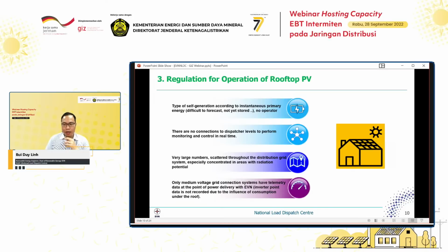Here are some features of rooftop PV operation in Vietnam. First, it is a kind of self-generation based on primary energy, which is very difficult to forecast and not yet stored, so there is no operator for this kind of rooftop PV, and no connection to the dispatch level to perform monitoring and control in real time. There is a very large number of such systems in Vietnam, more than 100,000 connected to the grid and scattered throughout the distribution system, especially concentrated in areas with high radiation potential. The last feature is that only medium voltage grid-connected systems have telemetry data at the point of power delivery with EVN.